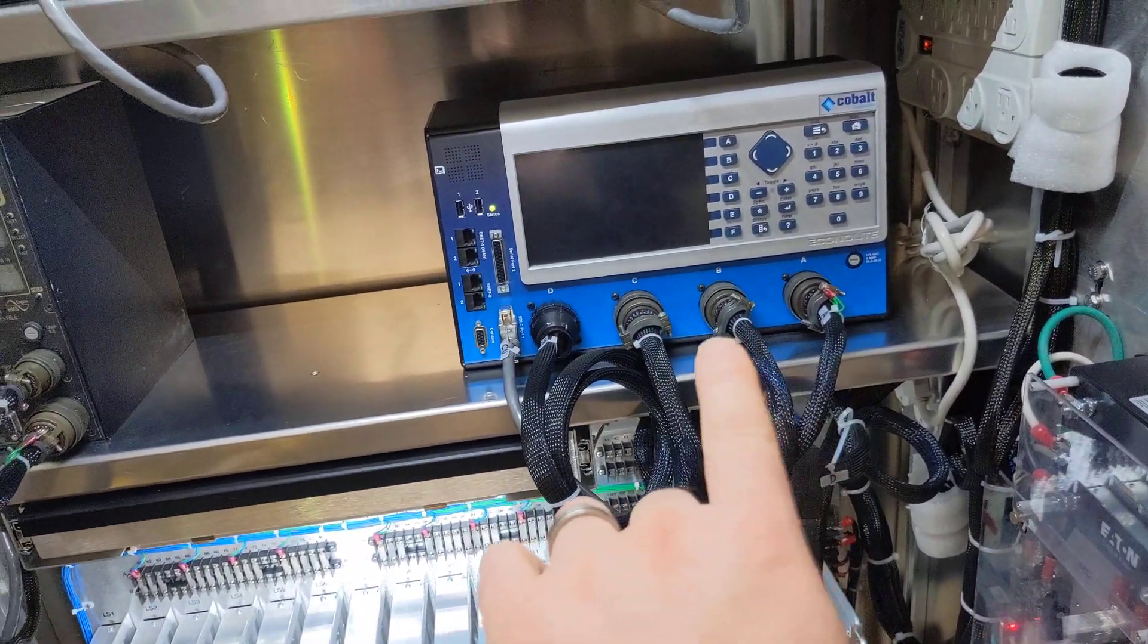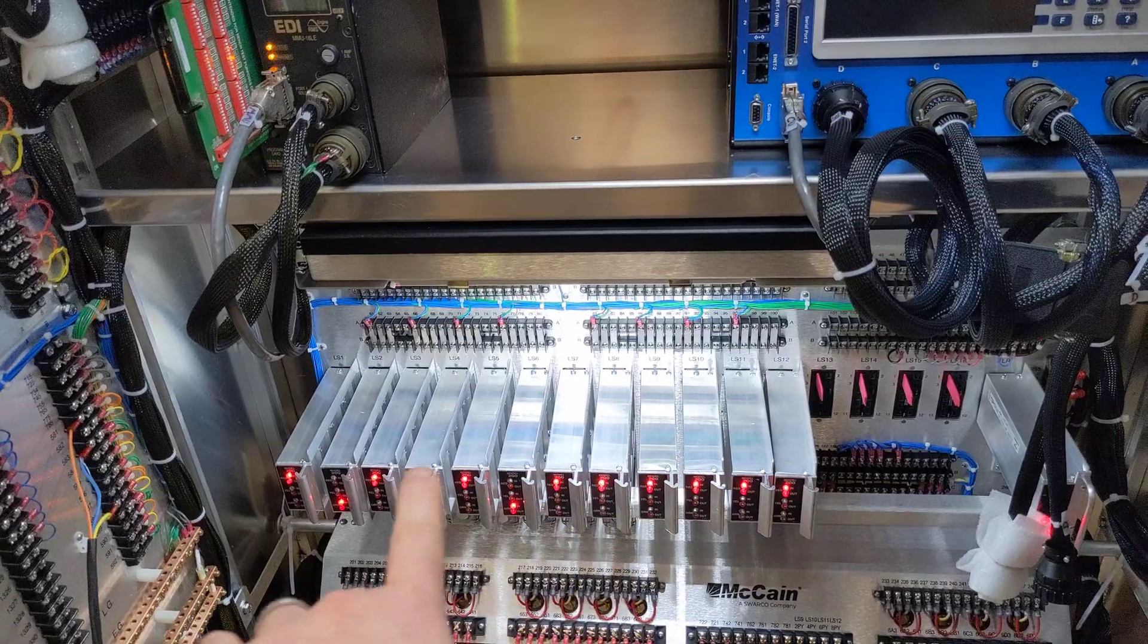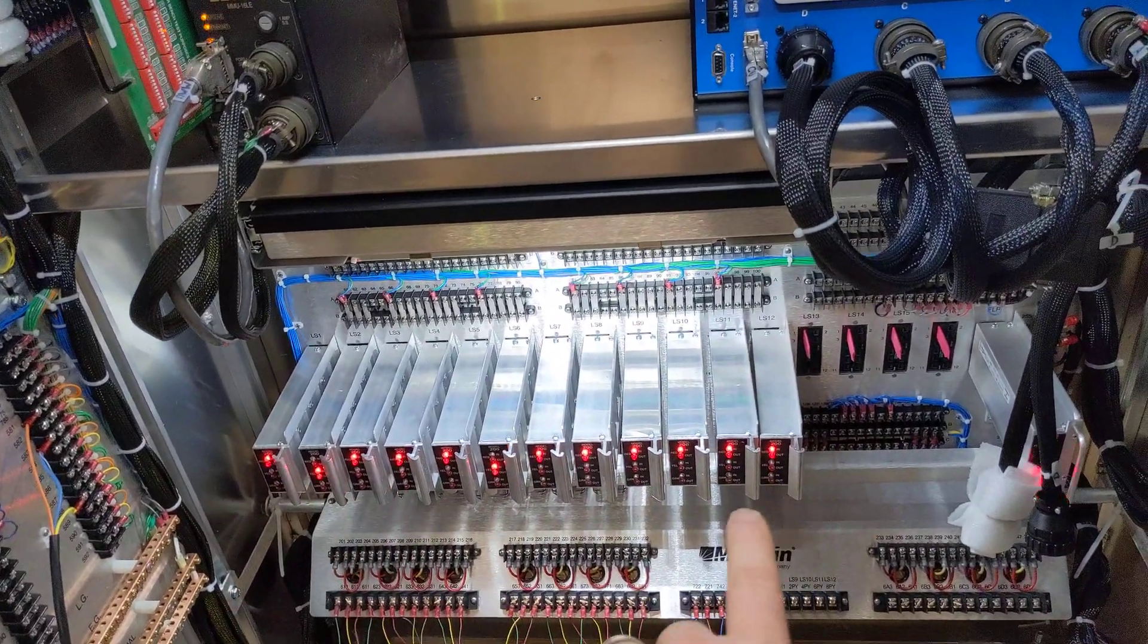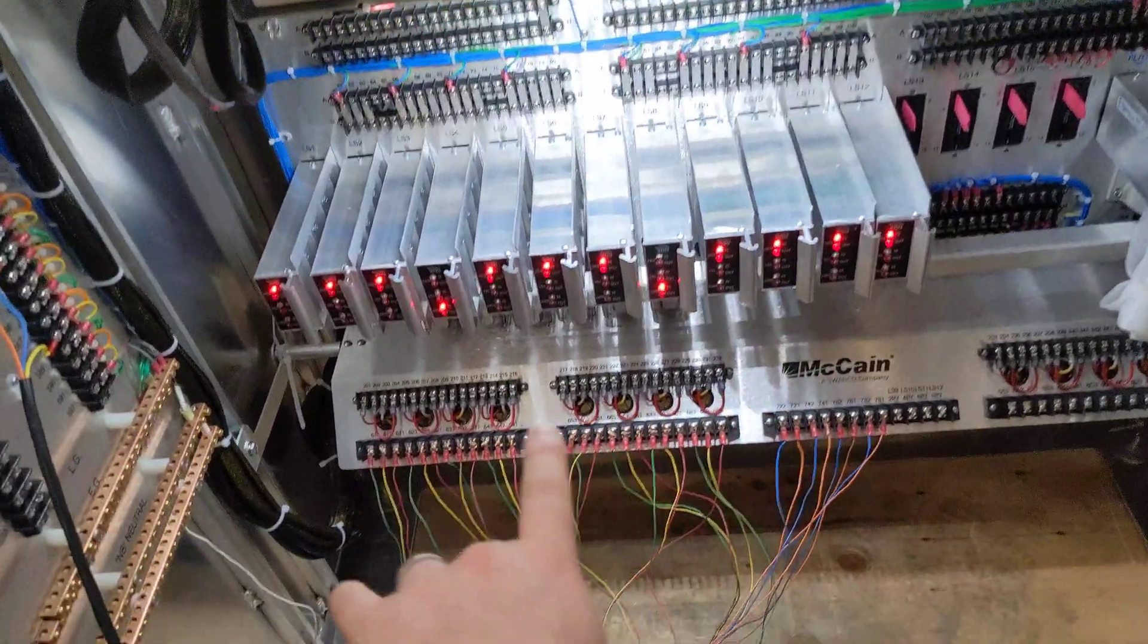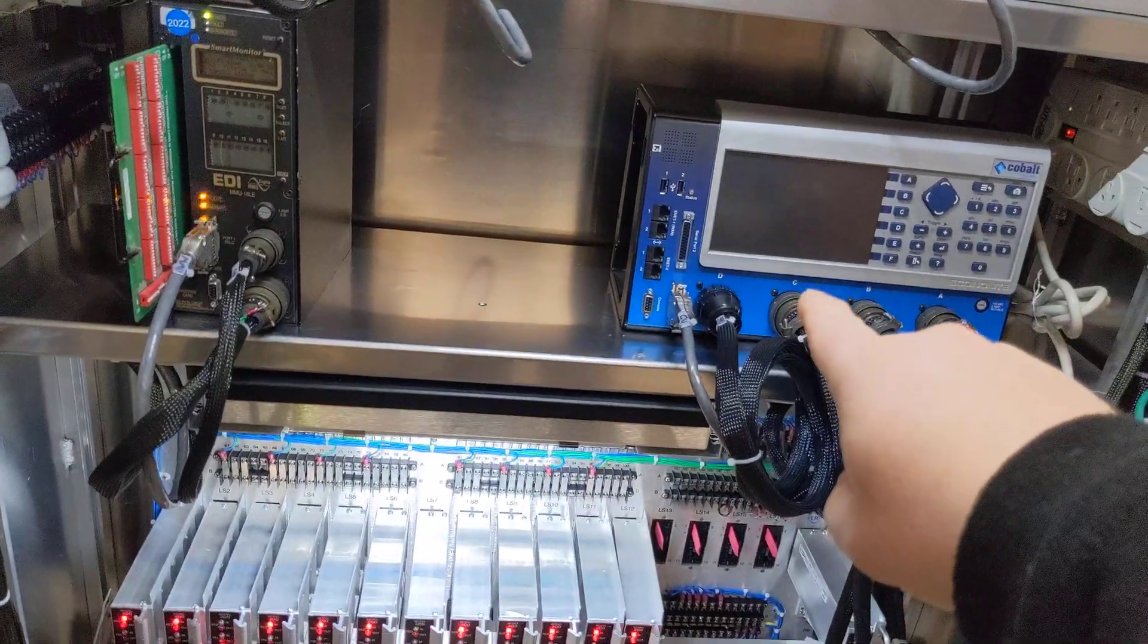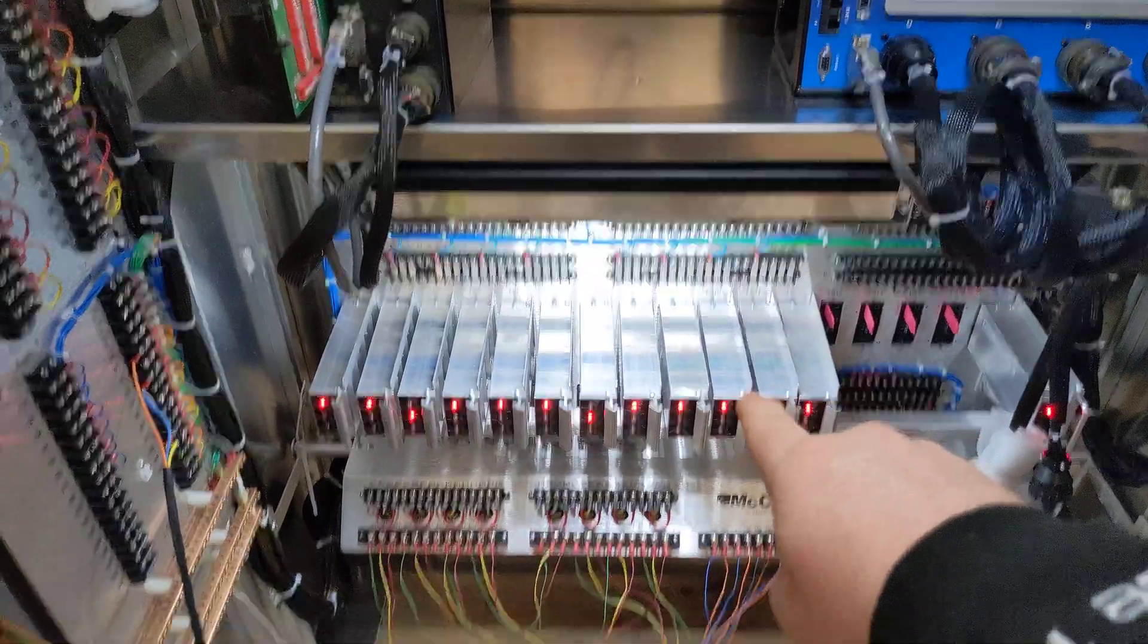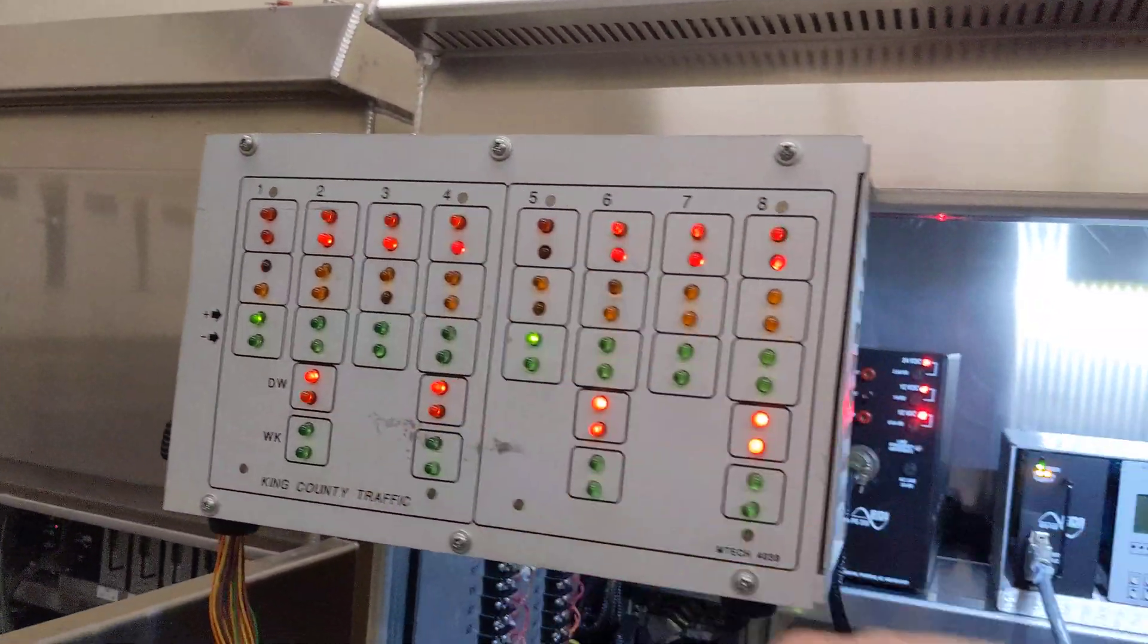Driving the 24-volt outputs from the controller to the inputs of the load switch, which in turn drives the 120-volt output of the load switch into the field wiring. So once again, 24-volt DC and logic ground control these guys, which in turn drives the power out to the field indications, which then make the lights do the thing. See, they do the thing.